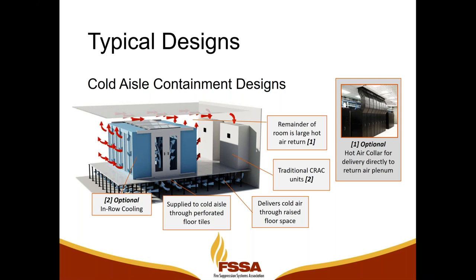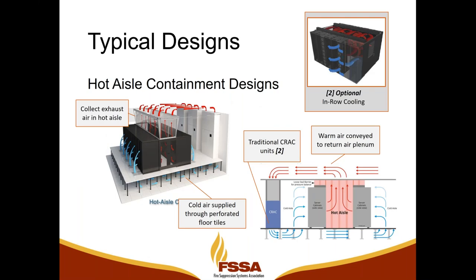or maybe even in another room. One variant of that is hot air collars, where instead of the whole room being our cold aisle where we're providing that cooling air, we actually duct using chimneys straight up to the ceiling or to a duct going back to the cooling units, using these collars. So that's one variant of cold aisle containment. Hot aisle containment is where we build a large duct or a large collar around the entire hot aisle and allow that hot air to be separated from the cold air, and it goes up.